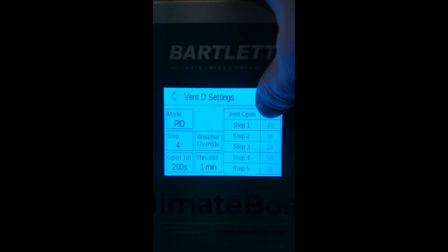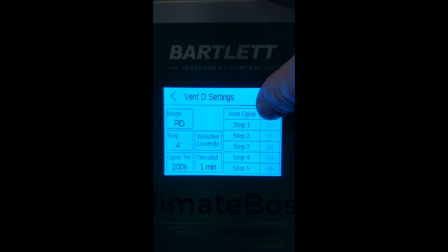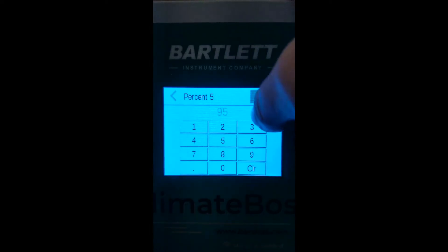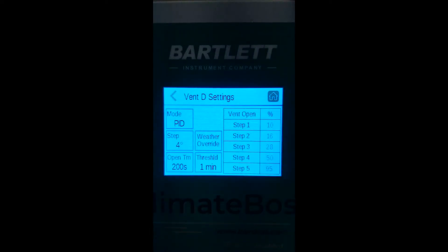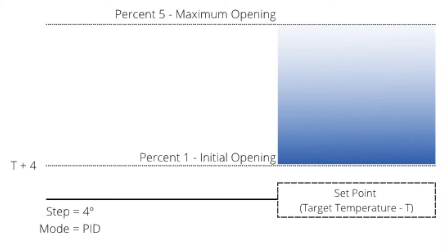In PID mode, you still need to set the step size. You also need to set the initial opening, or step one, at 10 percent. Step five is the maximum amount of opening for the vent — currently this is 99 percent. You can click the number and edit this if you'd like it to be a lower percentage. In PID mode, step two, three, and four are disregarded. Step one and five are used as guardrails, and the controller automatically adjusts the open percentage based on the PID calculations.